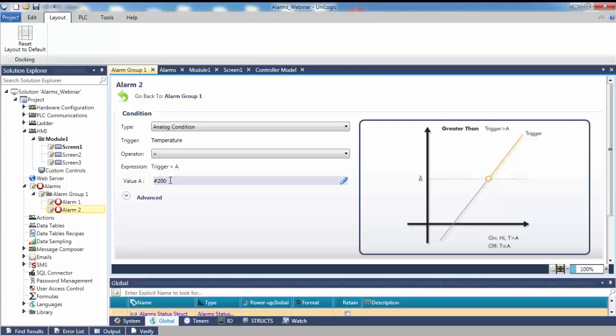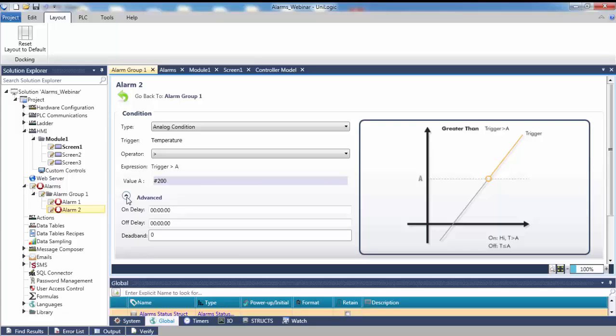Note that because we selected the analog condition, we can set a dead band range around the analog alarm trigger values. A dead band is useful for alarms whose trigger values may fluctuate near the alarm trigger value. When the alarm's trigger reaches its trigger value, the alarm turns on. However, the alarm does not turn off until the value falls below the dead band range. For example, if your alarm's trigger value is 100 and the current value is 100, then the alarm will trigger. However, if you had a dead band of 5, the alarm would not turn off until the alarm trigger value fell below 95.